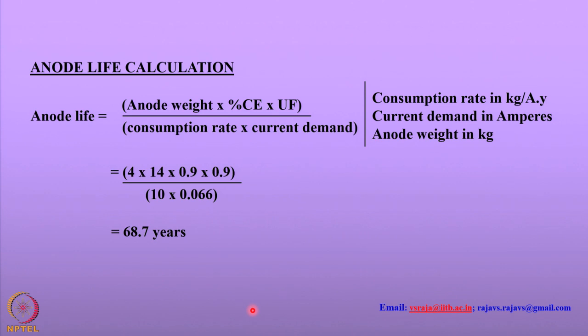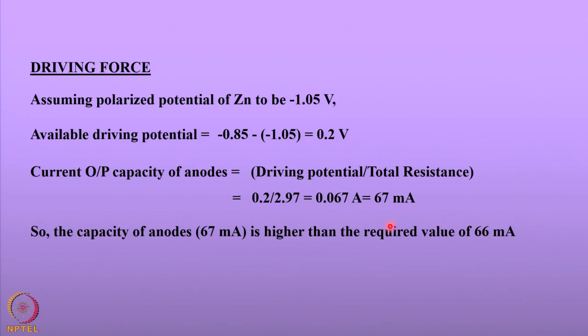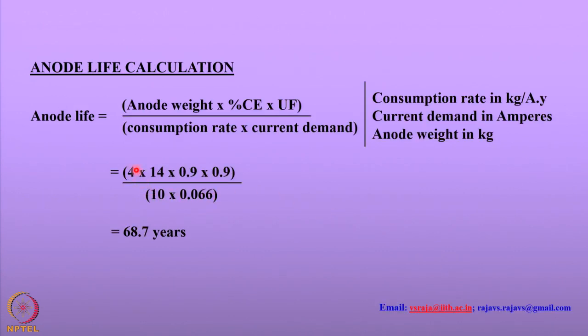However, there are concerns as zinc anodes passivate over time. Also, 4 anodes barely provide the required current of 67 milliamperes vs. 66 milliamperes. If the number of anodes is increased to 5, the life would be much longer, meaning zinc is being wasted. Therefore, we should avoid having more anodes than needed. One alternative is to consider a magnesium anode instead.